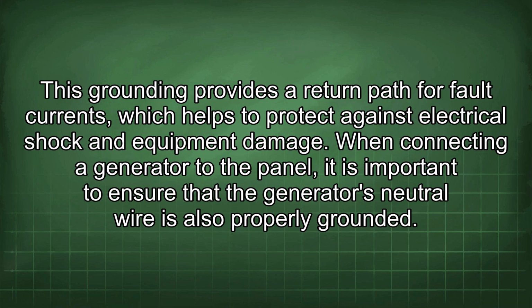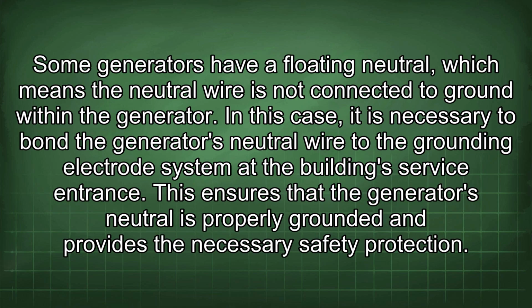When connecting a generator to the panel, it is important to ensure that the generator's neutral wire is also properly grounded. Some generators have a floating neutral, which means the neutral wire is not connected to ground within the generator. In this case, it is necessary to bond the generator's neutral wire to the grounding electrode system at the building's service entrance. This ensures that the generator's neutral is properly grounded and provides the necessary safety protection.